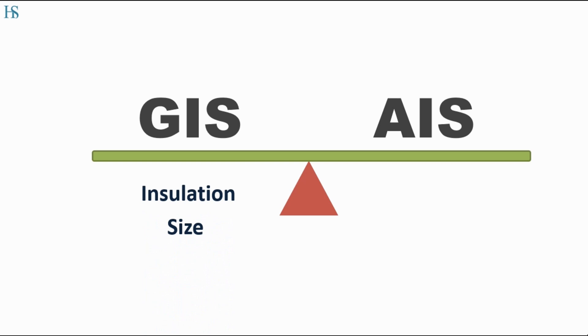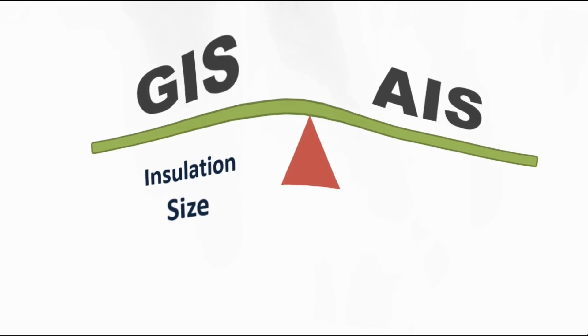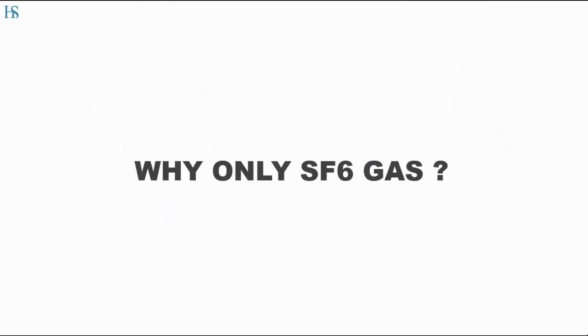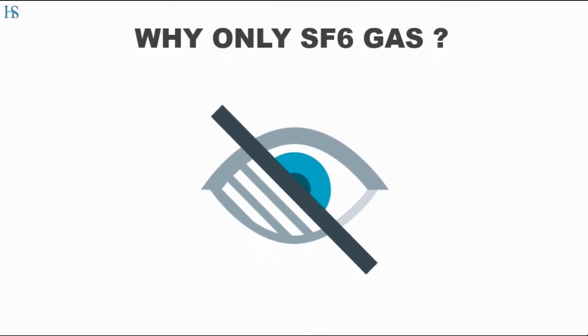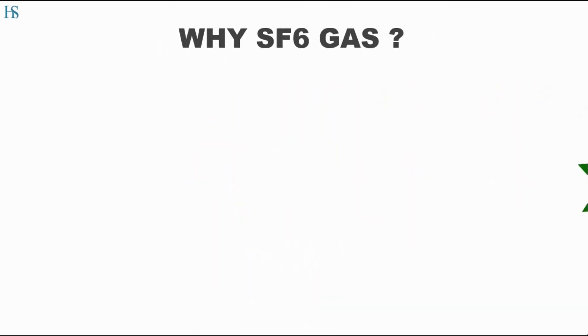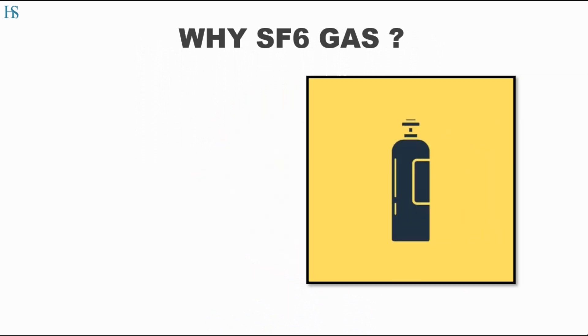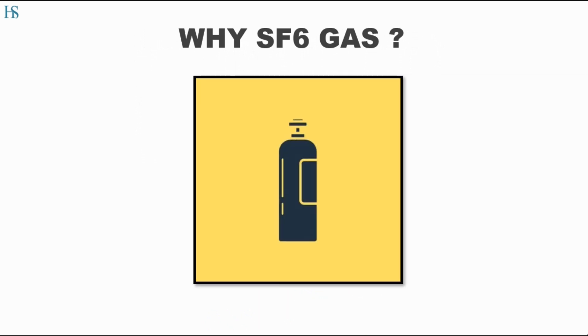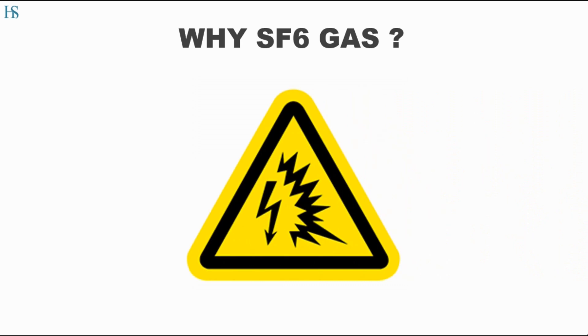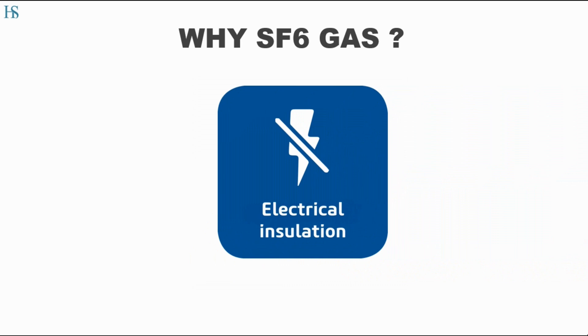So now why have we moved from AIS to GIS? This is because of the reduction in size by approximately 70% in GIS. Why only SF6 gas? SF6 gas exhibits properties such as it is colorless, odorless, non-toxic, and an inert gas which means it does not react with any metal. It has excellent arc-quenching properties and it works as a good electrical insulator.